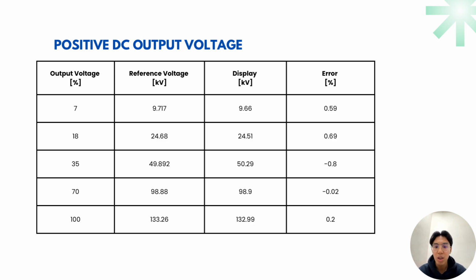0.59%. As we ramp up the system to its peak at 100% output, the reference voltage reached a massive 133.26 kilovolt. The display tracked this incredibly closely at 132.99 kilovolt, resulting in an error of only 0.2%. The key takeaway from this dataset is the remarkable consistency of the instrumentation. Across the entire voltage sweep, the percentage error never exceeded 0.8%. This indicates a highly linear and reliable tracking response between our high voltage control kit and the monitoring display.